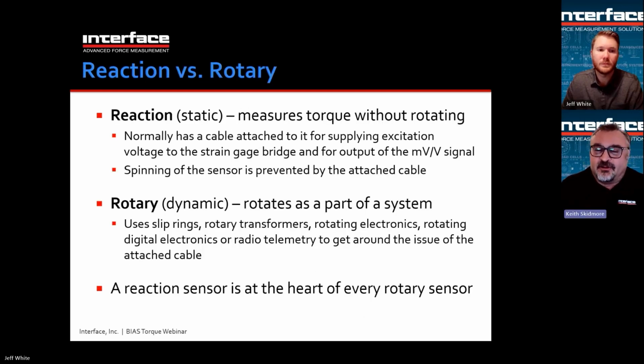So reaction or static, and we'll use that term interchangeably, measures torque without rotating. Basically, if you have a regular Wheatstone bridge type sensor, there will be a cable attached to the sensor for the power to the bridge and the signal coming from the bridge. With a static sensor, that cable is attached directly to the sensor. If you were to spin the sensor, the cable would spin along with it. So the sensor can rotate through some minimal amount of rotation, but if it were to spin round and round, the cable would get wrapped up. So a reaction sensor has a cable attached to it, which prevents it from spinning round and round.